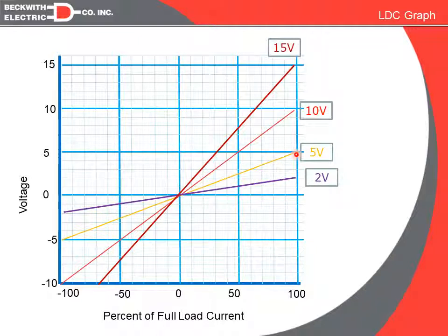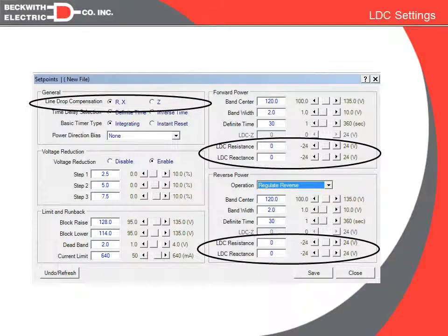be using 125. But if the DG was fully online, we would actually be subtracting, and we would actually be lowering the voltage at the substation bus, which would not be a desirable thing and would typically cause low voltage. And we're going to be covering that more in detail in the next session on line drop compensation. But here would be our typical settings in the control.